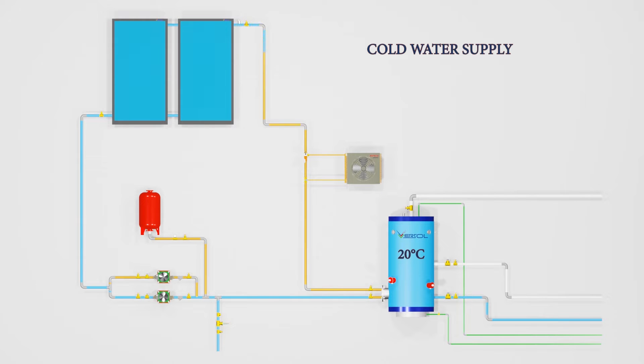While filling primary side circuit, make sure feeder line inlet pressure is as per requirements and then open the feeder valve. Air vent and safety valve must be in open position till the circuit gets filled.